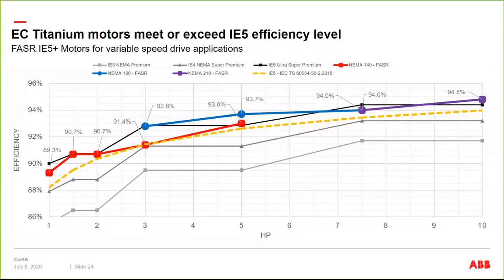Now, what the IE bands are, it's really an IEC standard. And all it really means is that for each band of efficiency, like going from IE3 to IE4, there has to be 10% less losses in the motor. And less losses means higher efficiency. So what we're talking about here today is the IE5 efficiency band, which is this black line here. Now that's for the motor only, but none of the motors in existence today, there are no IE5 motors that run across the line. So IEC came back and came up with a standard, which is this dotted yellow line, which is the IE5 standard for the motor with a drive. And you can see all of our products are at or above. So in this case, this black line is the true IE5 standard. If you look at a 5 horsepower, it's 93.7%.